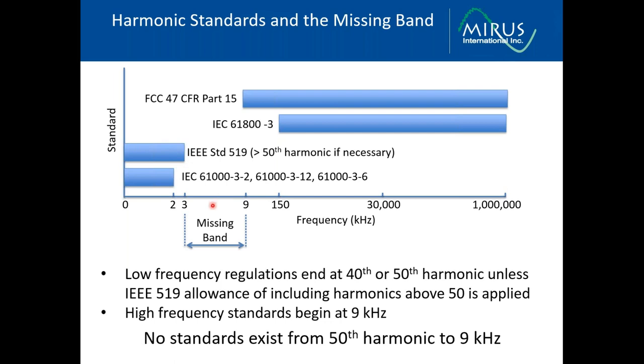International standards, IEC, various standards here, are all set at the 40th harmonic. Typically, it's applied on 50 hertz systems. So in that case, it would cover the harmonics up to 2 kilohertz. For the higher frequency, or EMI and RFI, or radiated harmonics, typically IEC 61800-3 is used to limit those. And this is the reason why many variable speed drives are equipped with EMI RFI filters. That standard starts at 150 kilohertz and goes above that.